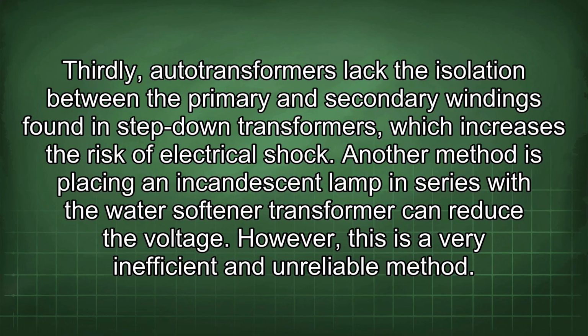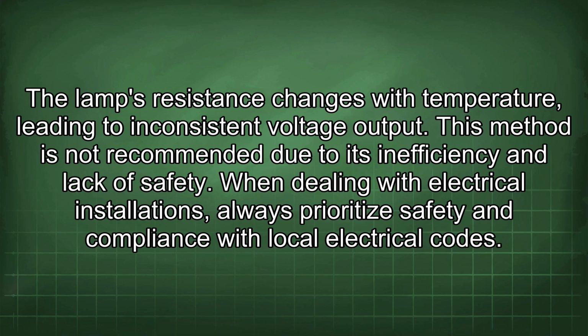Another method is placing an incandescent lamp in series with a water softener transformer to reduce the voltage. However, this is a very inefficient and unreliable method. The lamp's resistance changes with temperature, leading to inconsistent voltage output. This method is not recommended due to its inefficiency and lack of safety.